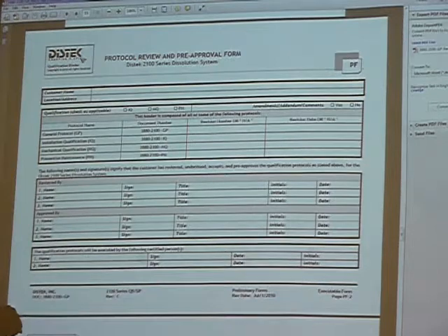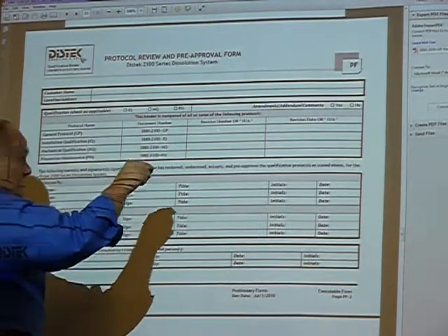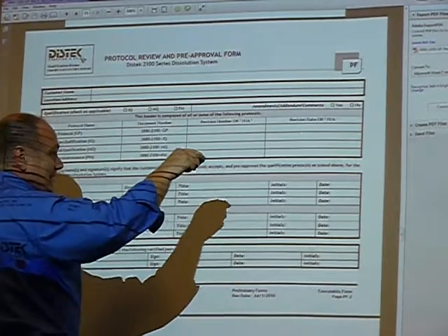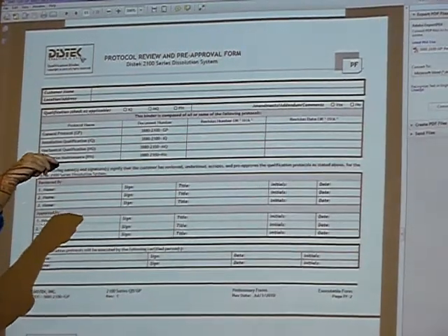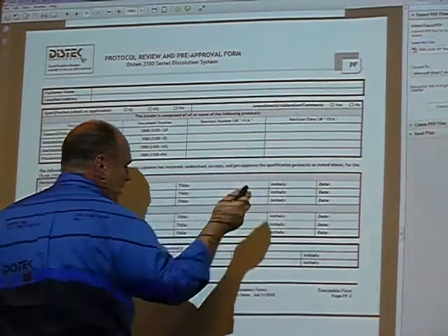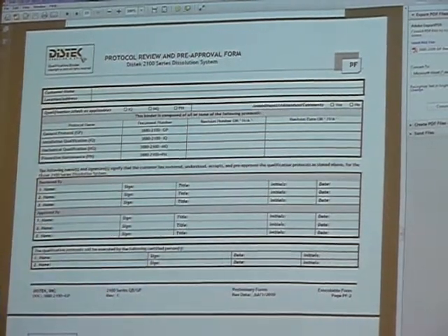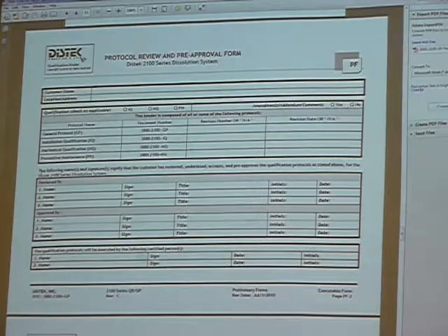Typically here in our company, here in the United States, whatever we're performing, we do GP, we'll put the revision number and the date. If we're not performing it, well, GP will be there. The next one's IQ. If you're performing an IQ, revision and date go in there. If you're not performing it, we typically NA it and initial and date it.